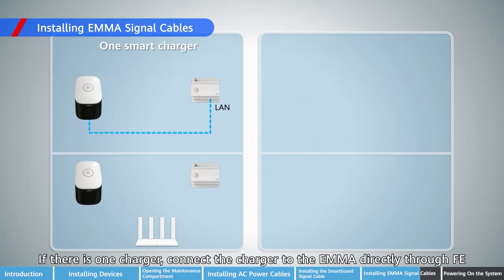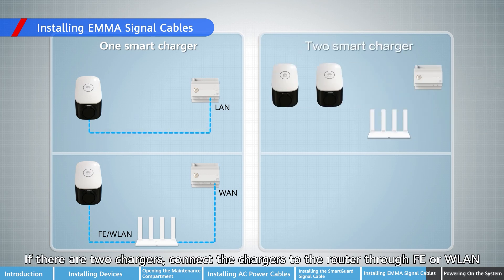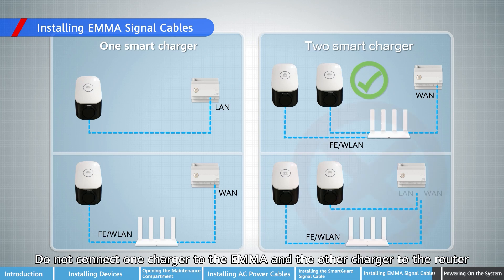If there is one charger, connect the charger to the EMMA directly through FE, or to the router through FE or WLAN. If there are two chargers, connect the chargers to the router through FE or WLAN. Do not connect one charger to the EMA and the other charger to the router.